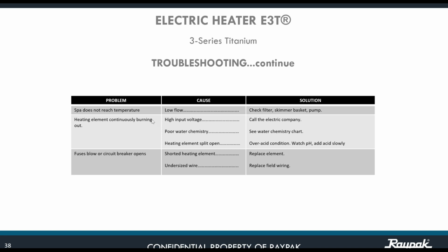Okay, another possible cause for the heating element continuously burning out might be a heating element split open. The solution for that is you did an over-acid condition. You need to watch the pH and add the acid slowly. Remember that you are adding the acid to the pool, to the whole mass of water in the pool, not to the skimmer. Okay, another problem might be fuses blown or a circuit breaker opening. Well, there is a shorted heating element, you need to replace it. And if you have an undersized wire, you need to replace it with the right one. Remember that I explained what size of wire you need for the specific kilowatt unit you are installing in your spa or pool application.